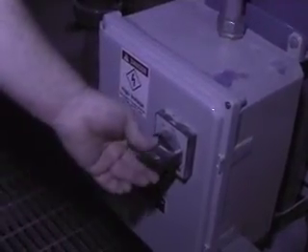I don't know why it's off. Do you know why the cooling tower system's off in general? I thought it was Johnson's. Somebody's got the VFD off outside, and somebody's got all the condenser water pumps off, and somebody's got this off. So let me go ask. If it's not you guys, we need to figure out why everything's off.